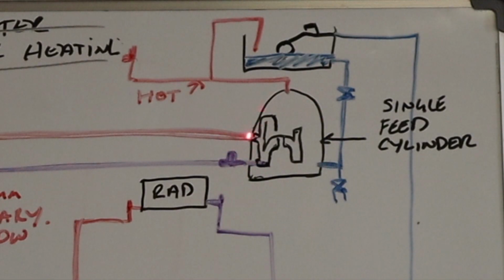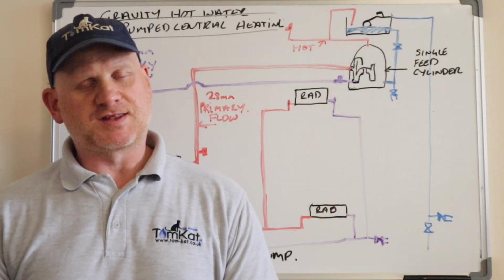So let's have a look at this cylinder more closely. So this is what we call a single feed cylinder, or its trade name of PRIMATIC. Single feed meaning there's only one system. So the one system allows the water to come in to the cylinder, and the water what's in the cylinder will then feed the central heating. We will have a look at this more closely in a second. So that's the pipe layout for this system.